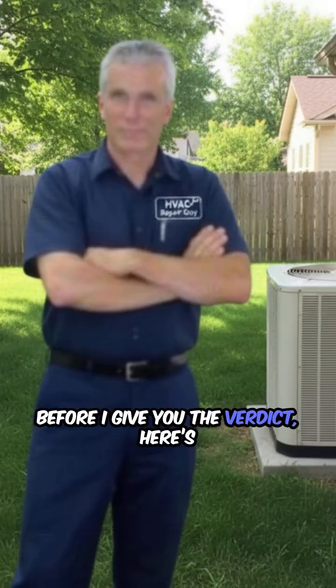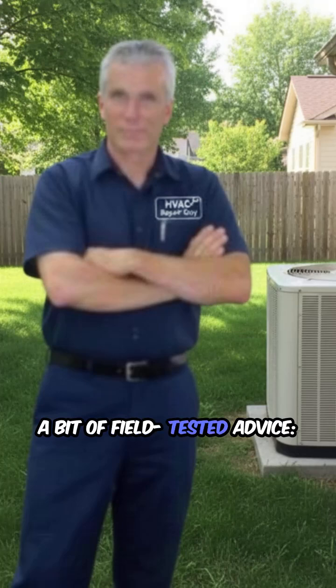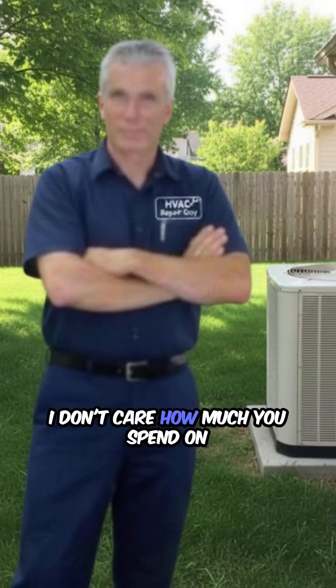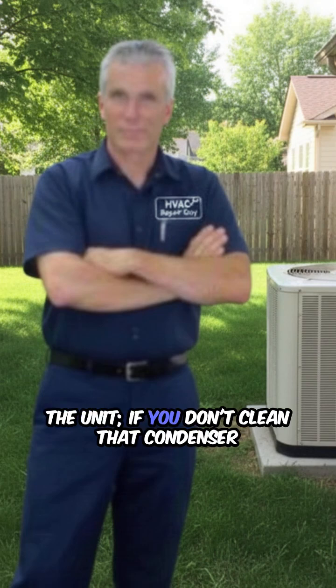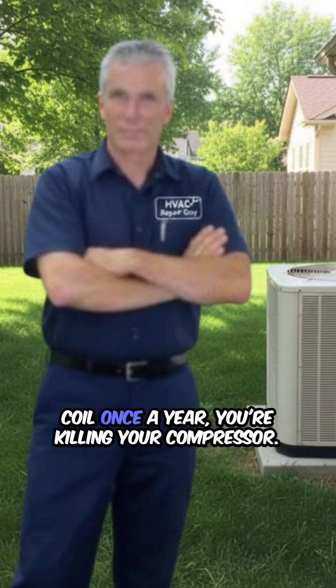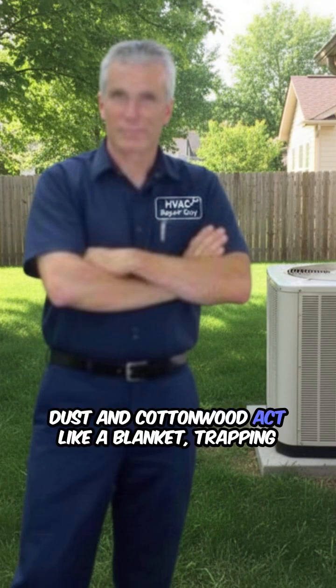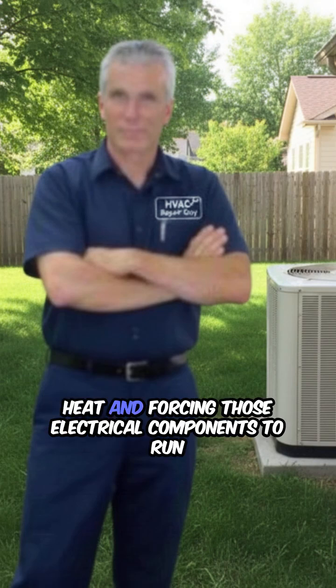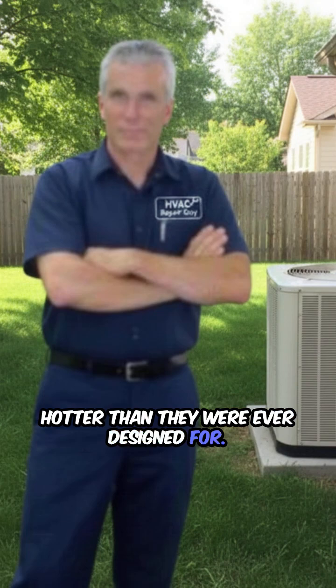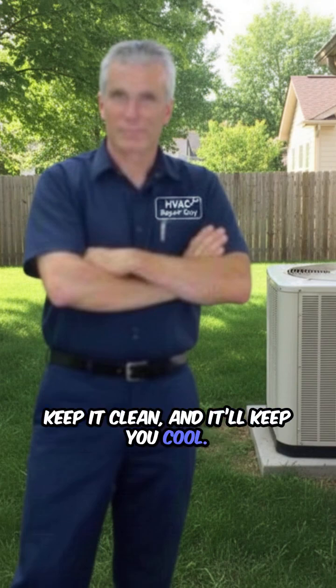Before I give you the verdict, here's a bit of field-tested advice. I don't care how much you spend on the unit. If you don't clean that condenser coil once a year, you're killing your compressor. Dust and cottonwood act like a blanket, trapping heat and forcing those electrical components to run hotter than they were ever designed for. Keep it clean and it'll keep you cool.